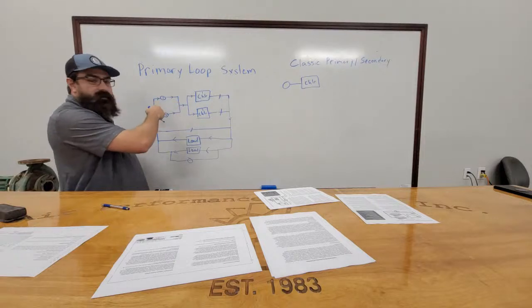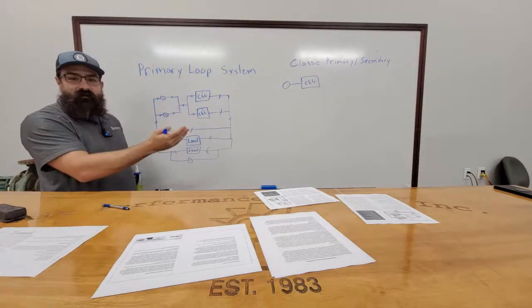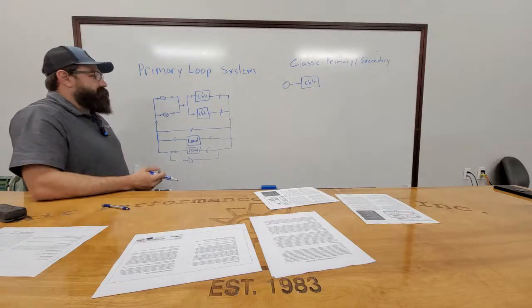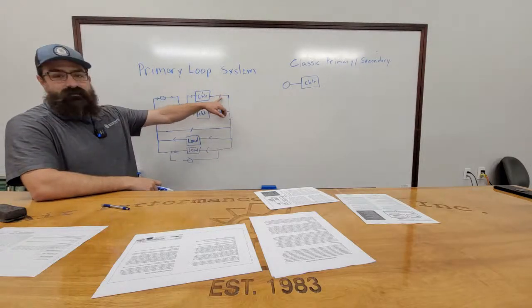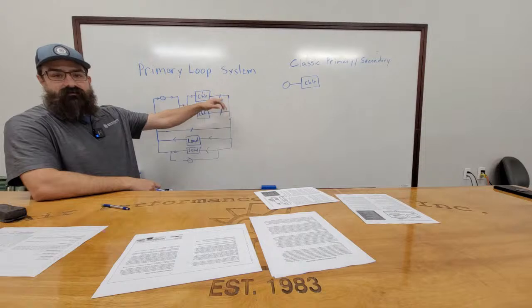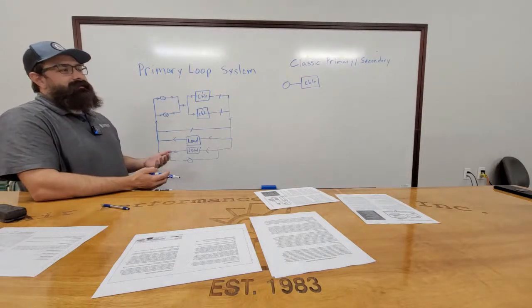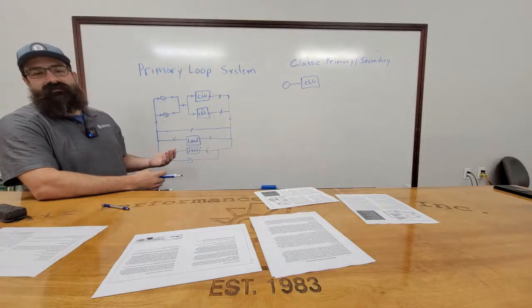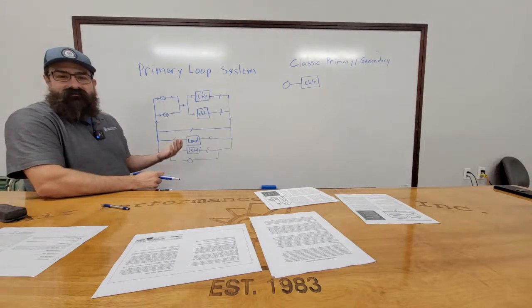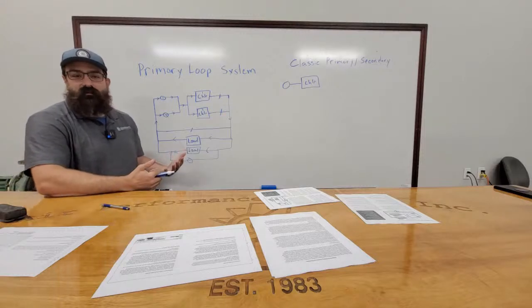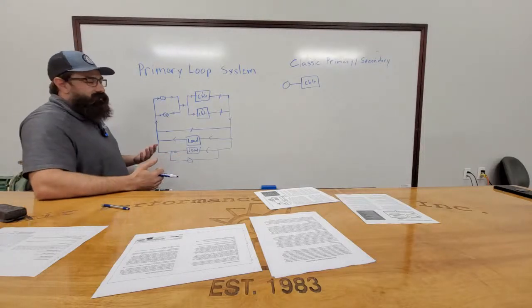Other systems will start a pump, let it deadhead for a couple of seconds while the valve opens. It really just depends on how it was programmed and built. I always recommend having an end switch on here. Open the valve first, then start your pump. That way you don't deadhead. But in a deadhead scenario, you're talking a couple seconds, maybe a minute max while that valve drives open. As soon as it cracks, you're going to start having flow. So you're not going to just sit there and spool the pump all day. That really shouldn't hurt it.